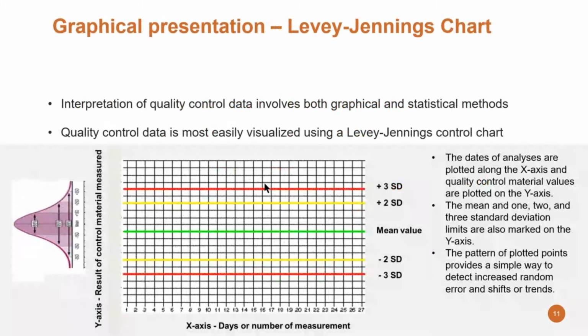So this is the graphical presentation, which we call the Levey-Jennings chart. It is an interpretation of quality control data, using both graphical and statistical methods. Quality control data is most easily visualized by this chart. Here you see on the left side the bell-shaped curve, the normal distribution curve, or the Gaussian curve, whatever you want to call it. That's the curve which shows a normal distribution. And in the center of the slide, you see the Levey-Jennings chart. The green line is the mean value. The yellow line is 2 standard deviations plus and minus, and the red line is 3 standard deviations plus and minus.